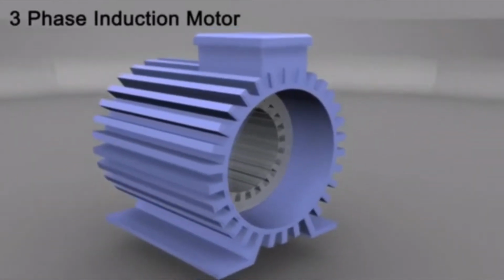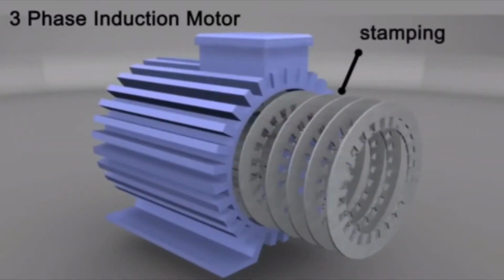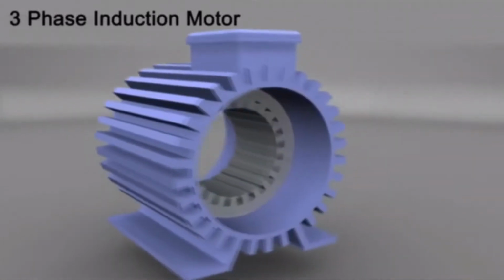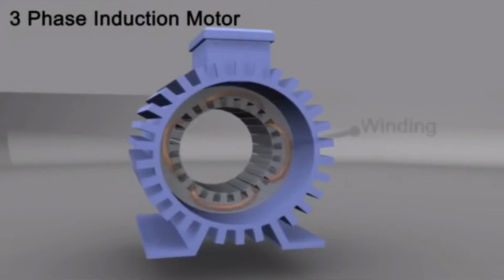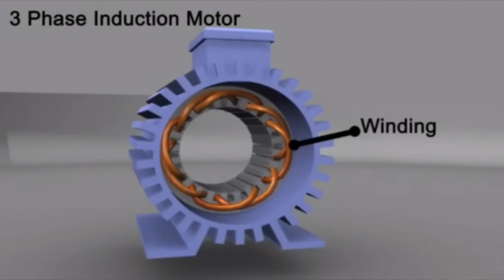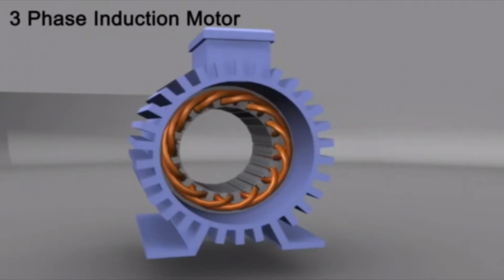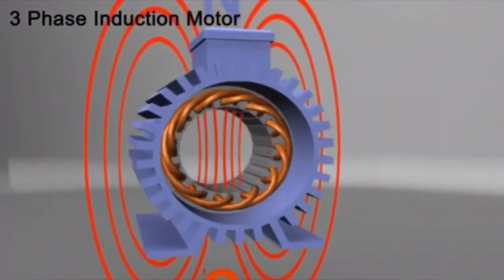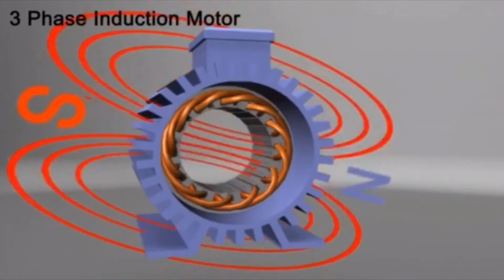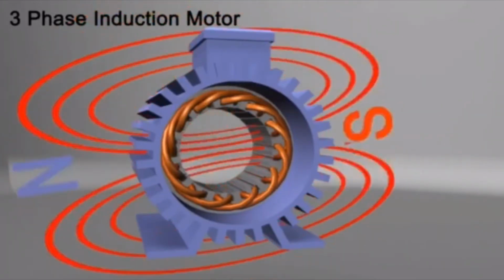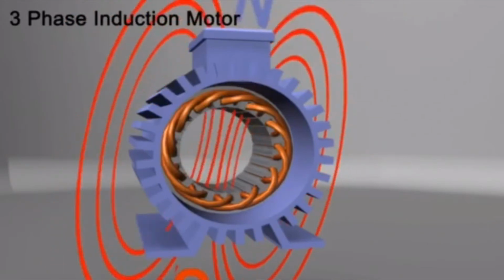Stator. It is made up of a number of stampings in which different slots are cut to receive the three-phase winding, which is connected to a three-phase AC supply. The three-phase windings are arranged in such a manner in the slots that they produce a rotating magnetic field after AC supply is given to them. Usually, windings are kept at different pitch circles.